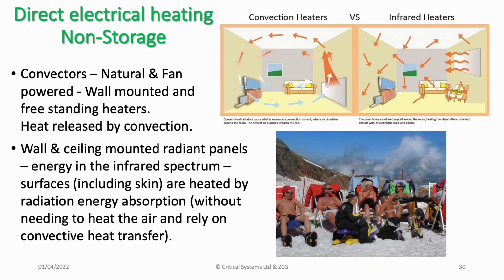And the air in the space heats us, makes us feel comfortable, and also imparts heat energy to the cold surfaces in the room. Another option is a radiant panel solution, and here wall or ceiling mounted panels radiate energy, and that energy is absorbed by the surfaces that it heats, including us, and that induces human comfort. And the picture below, which I thought was just a bit of fun, illustrates sunbathing in the snow, in the sun, where the radiant energy makes the human body warm in spite of the low ambient air temperature. So direct electrical heating is a possible solution and would become affordable in a small space or highly efficiently insulated building, home, apartment.